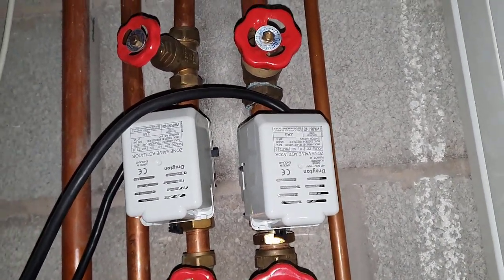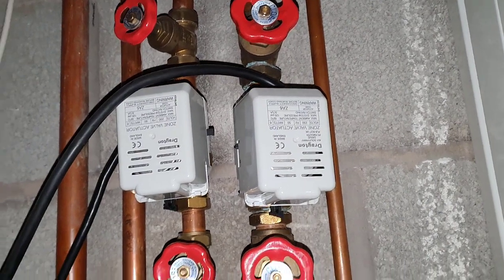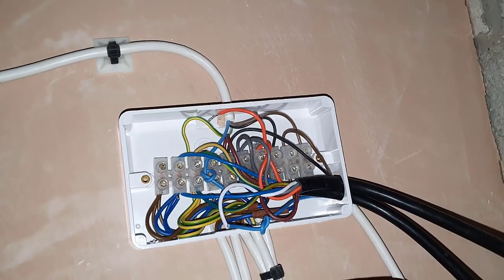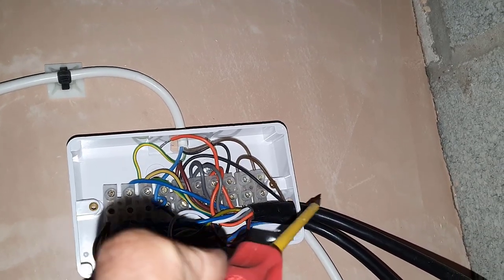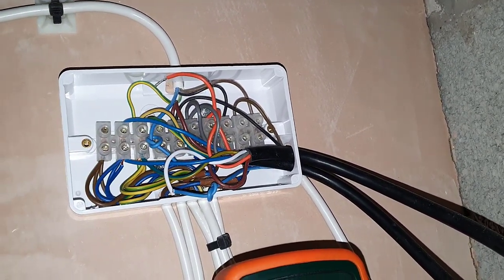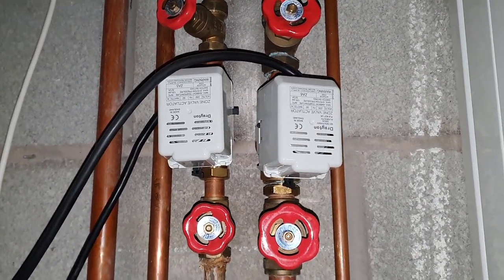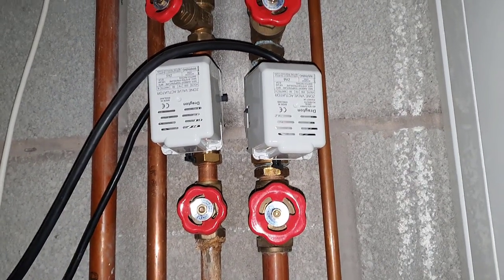So that's going to be it for this particular fault. These are quite easy to change — you'd have to do a drain down, then you can just take the head off and replace it, then rewire it using my technique which I've shown numerous times in my videos. Basically, cut the wire here first, pull it out, put your new wire in, and change one wire at a time so you don't get confused. And that's the full diagnostic for this situation on this particular valve.